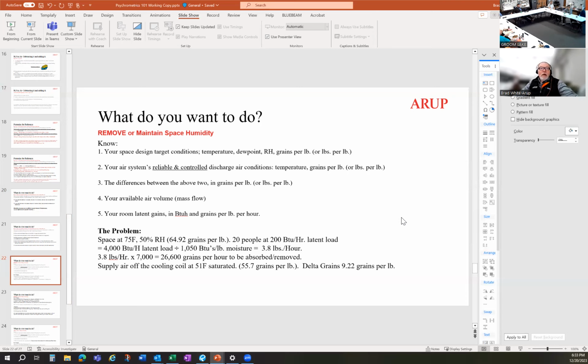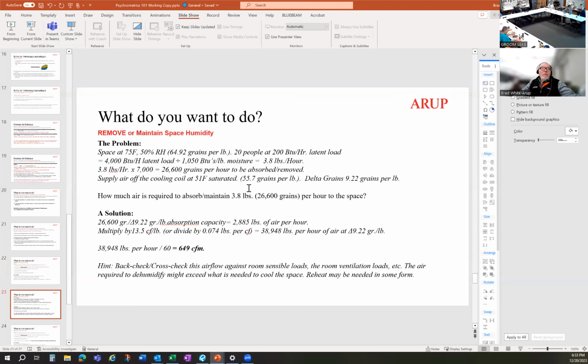But it breaks it down line by line how it's figured out what the delta grains per pound is. That's the problem. And then there's one solution: you have to move so many pounds of air per hour, how you multiply it out. And now you have your delta grains per pound. And you wind up with so many pounds per hour you're trying to remove, so many pounds of air you're moving, divided by 60, and that gives you your airflow rate, 649, call it 650 CFM. Now, this is more for my designers and engineers, but I think as contractors, you might find this handy as a back check.